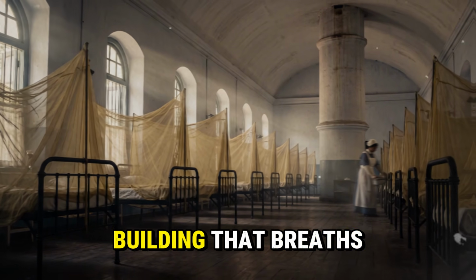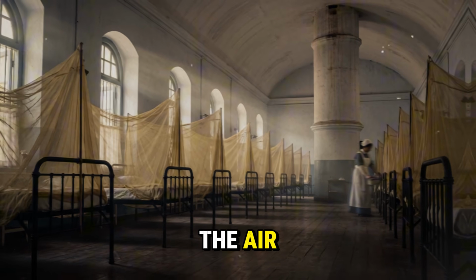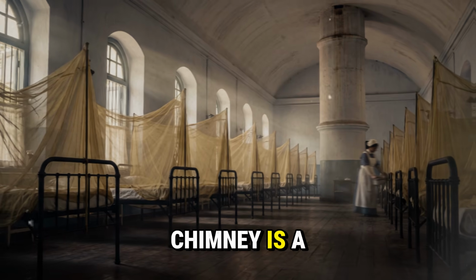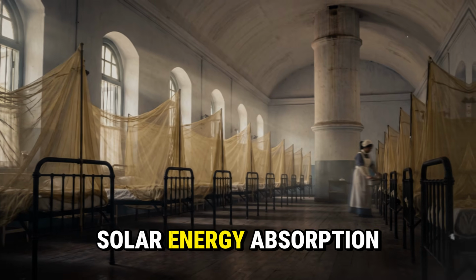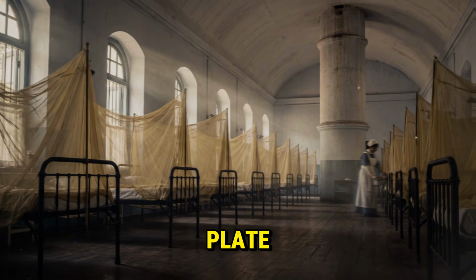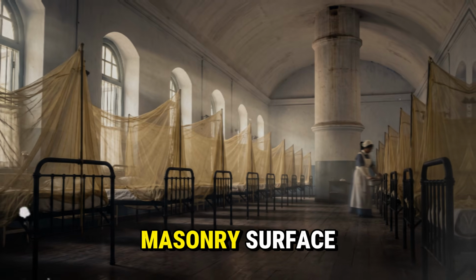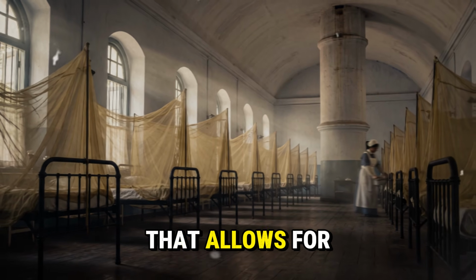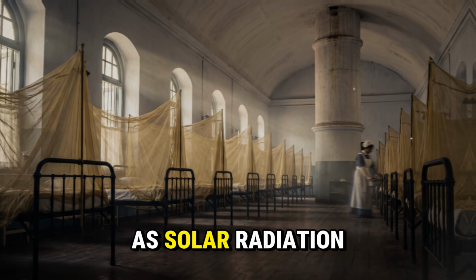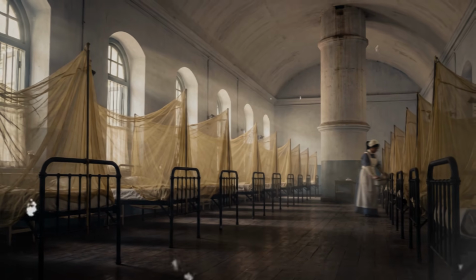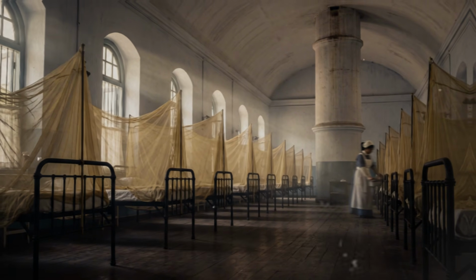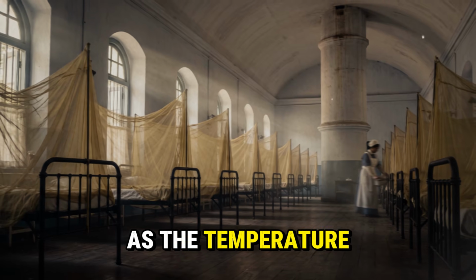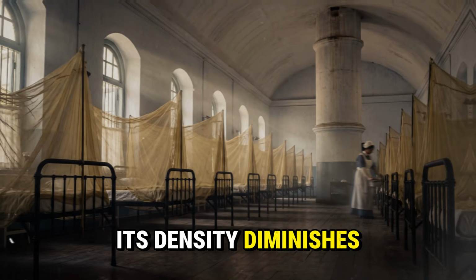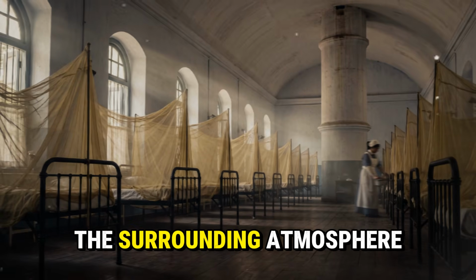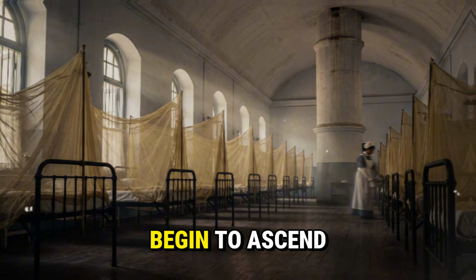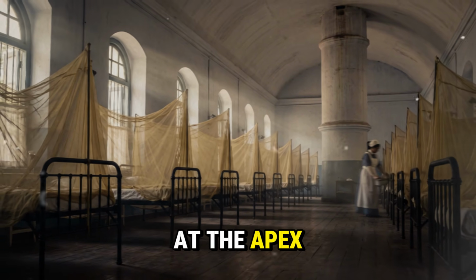To comprehend the engineering of a building that breathes, one must trace the path of the air. At its fundamental level, a solar chimney is a vertical conduit engineered to maximize solar energy absorption. It comprises a highly efficient absorber plate, typically a dark-colored metal or masonry surface, positioned behind a layer of glazing that allows for high light transmission. As solar radiation penetrates the glass, it strikes the absorber plate, where it is converted into long-wave thermal energy. According to the ideal gas law, as the temperature of the air within this shaft ascends, its density diminishes. The air becomes less dense than the surrounding atmosphere. These energized molecules begin to ascend rapidly towards the exhaust opening at the apex of the chimney.